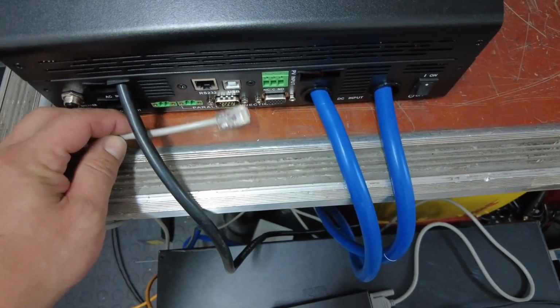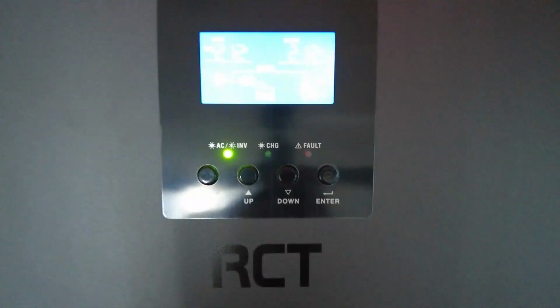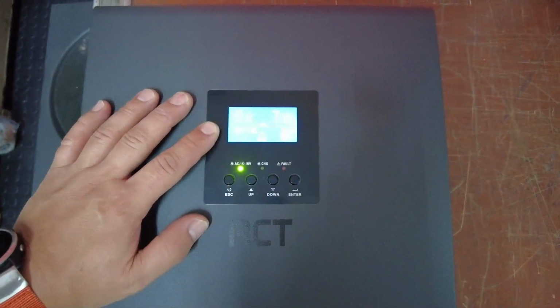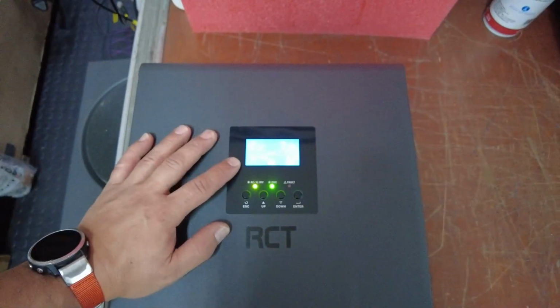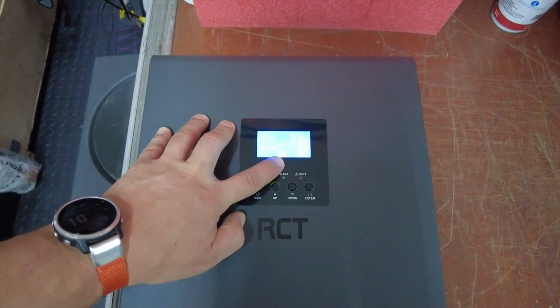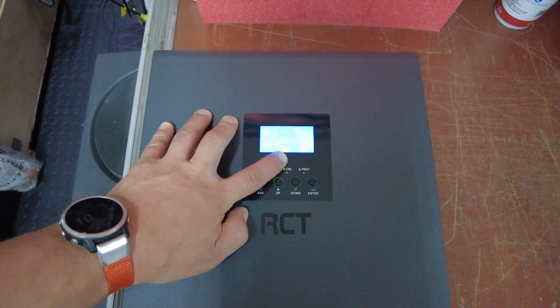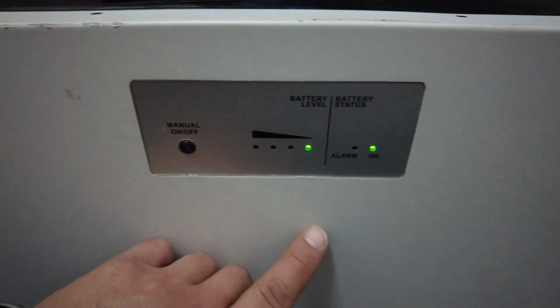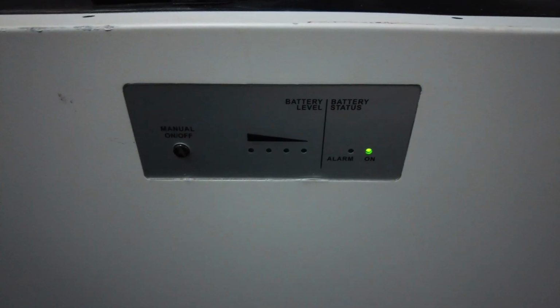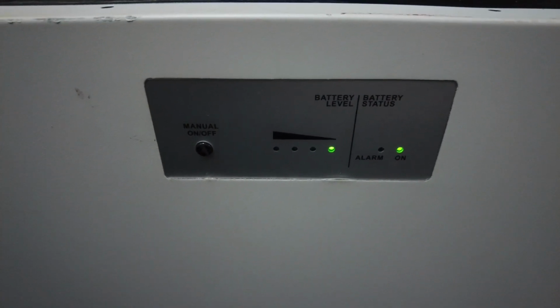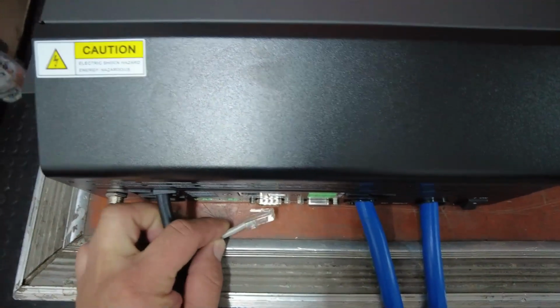I've deliberately disconnected this cable now while everything is on, so I can show you how it communicates. Apologies, you might not see this very clearly. Note that the battery capacity bars on the inverter currently show 2 bars charged, 2 bars SOC. But if you look at the battery, it's still on 1 bar SOC. The SOC levels do not match up, and that's because there's no communication currently.